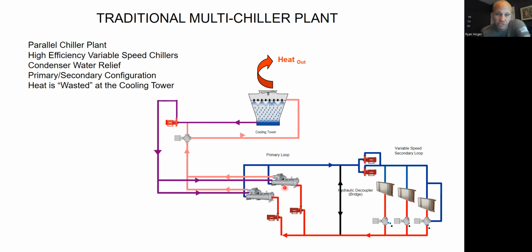And in this case, these 2 chillers are connected to 1 cooling tower. It could be that each chiller has its own cooling tower, or in this case, 2 chillers are sharing 1 cooling tower. Each chiller could have 2 cooling towers, so you'd have 4. There's all kinds of combinations of these things that you can do. So in reality, what happens on a chilled water system is you have 2 separate unrelated hydronic loops. I shouldn't say they're unrelated. They're related by the chiller, but pressure-wise and hydraulically, they're unrelated to each other.